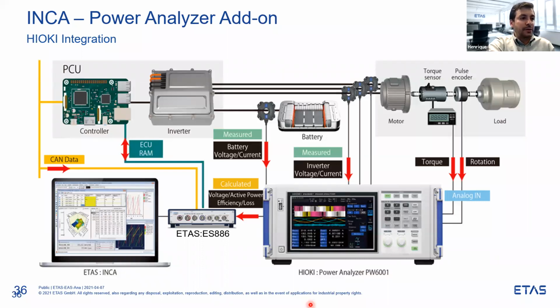So the target system consists here of an ECU with inverter, battery, motor, and load. The HIOKI Power Analyzer here, we are using the 6001, is measuring voltage and current between battery and inverter and on all three phases of the motor, and also using as analog input the torque and rotation from the motor. The Power Analyzer is connected to the ETAS box. This is the ETAS ES886 using an Ethernet cable. So there's an Ethernet cable between the Power Analyzer and the ETAS box.